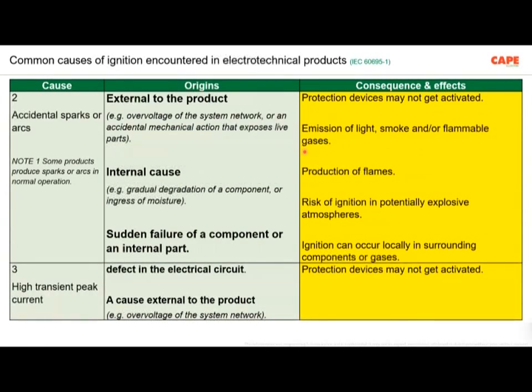Number two, accidental sparks or arcs. Here, we must understand that there are some electrical apparatus which inherently create arcing while operating. But that arcing is not supposed to ignite a fire. That is much more important. Then accidental sparks or arcs.